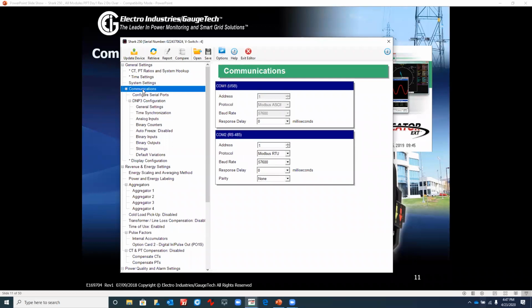The next area is the communications. Communications allows you to set up the ports, just like we talked about briefly early on, the COM1 USB port connection and COM2 485 connection. So those are what we would use if we were connecting to the meter over the optical port. We said USB, and I should say optical. Over the USB connection in the front panel, it would be COM1, and in this meter, your laptop that you're setting up to connect to this port would be assigned to COM8, as we saw before. So COM8 is going out of your laptop, connecting to this meter, which is represented here as COM1.